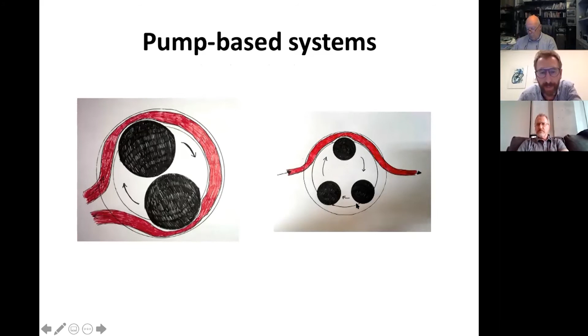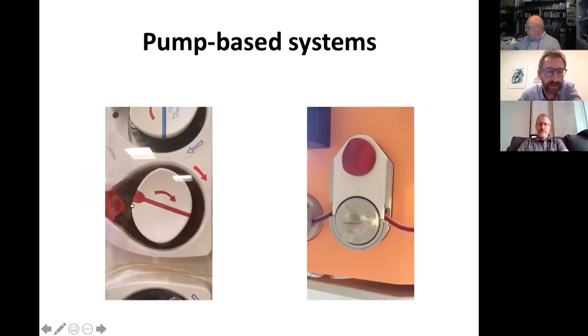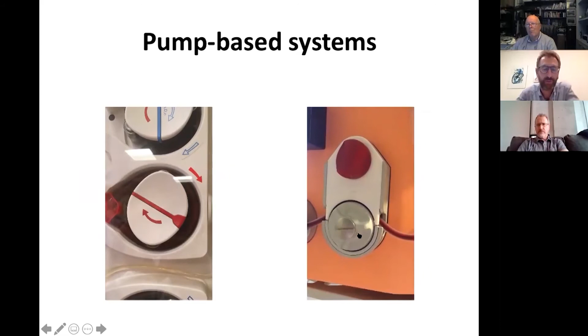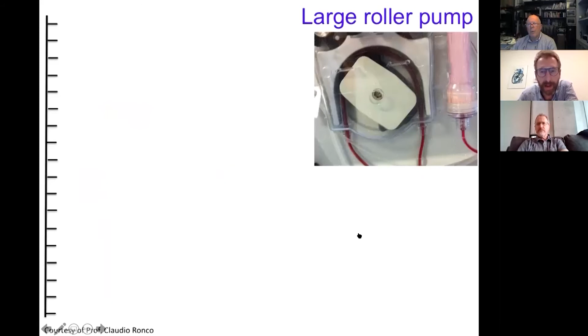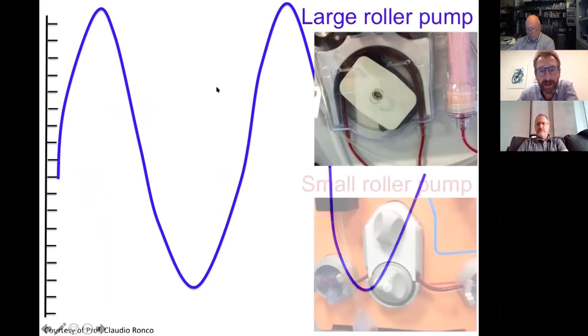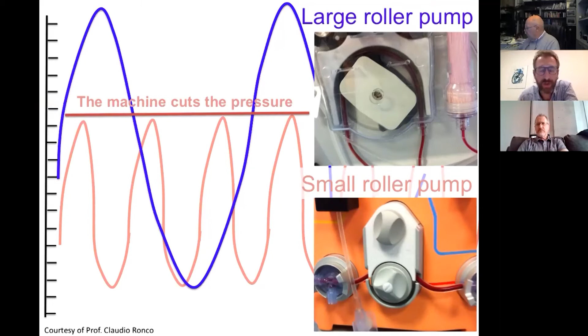So this is the typical movement of an adult pump, in which the pressure that these rotors give to the line is quite high. And this is the new type of pump that is incorporated in the CRRT NICU machine. As you can see, it tends to move faster, but the movement is more gentle. It's like a kind of cradle movement to the extracorporeal line. So this type of pump is associated with this type of pressure profile, and this type of pump is associated with this type of pressure profile. So this machine cuts the pressure, and this allows us to work with smaller catheters.